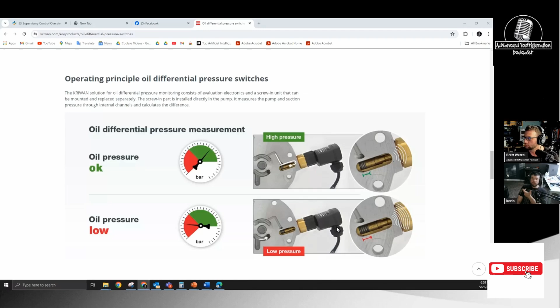So you said the schematic was drawn how again? It was drawn closed? It was drawn open. So it would be with oil pressure. Gotcha. But it didn't note it. And then the other thing that was a little confusing is the high pressure switch terminals on there are internally powered through the board, but only when it calls for it to run. So almost like when you use a current sensing relay for an oil timing thing, but instead of the current, and instead of the timing circuit for the oil, it's doing it for the high pressure.